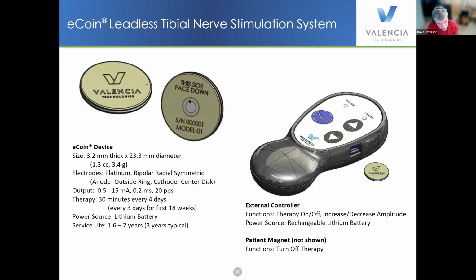As I mentioned, the stimulation parameters are 0.2 milliseconds, 20 pulses a second. And the output for this device ranges from 0.5 milliampere to 15 milliamperes. Around 8 milliamperes is where you tend to set this device up. And then the therapy is 30 minutes every 4 days. For the first 18 weeks, the device is pre-configured to deliver therapy every 3 days. And this is all automatic.